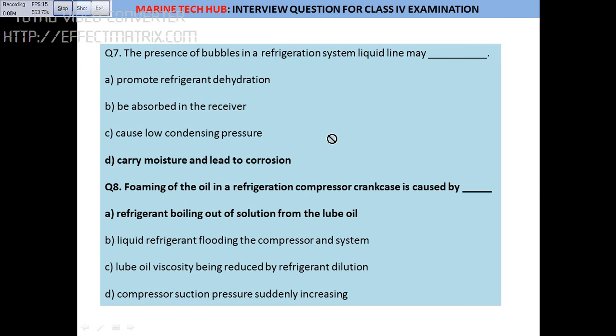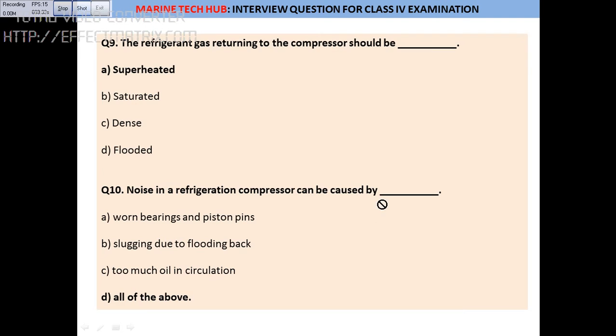Question 8: What causes foaming of the oil in the compressor crankcase? Foaming should not happen; if it is happening, that means the refrigerant is boiling out of solution from the lubricating oil. There are other reasons too — for example, if you put the wrong oil in the system and the compatibility is not correct, you will also get foaming.